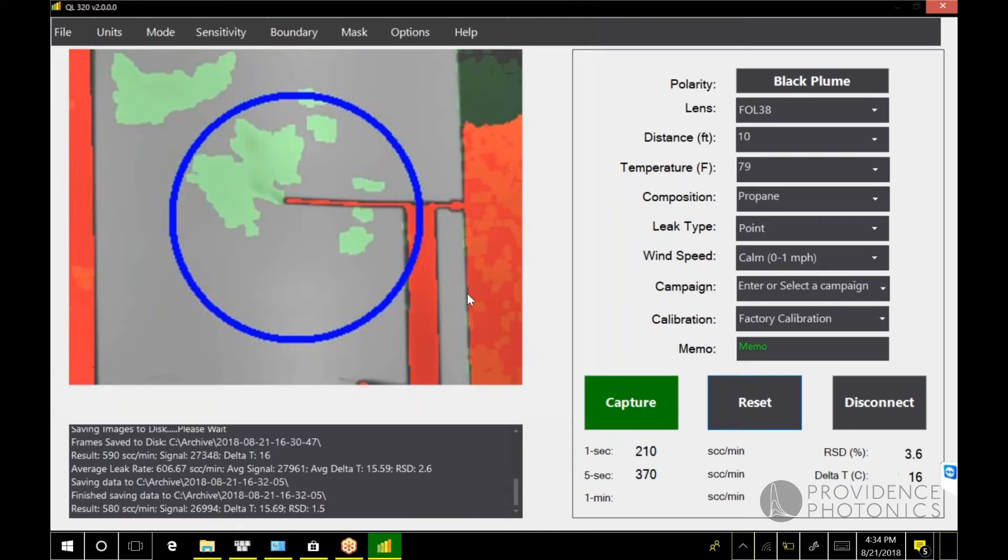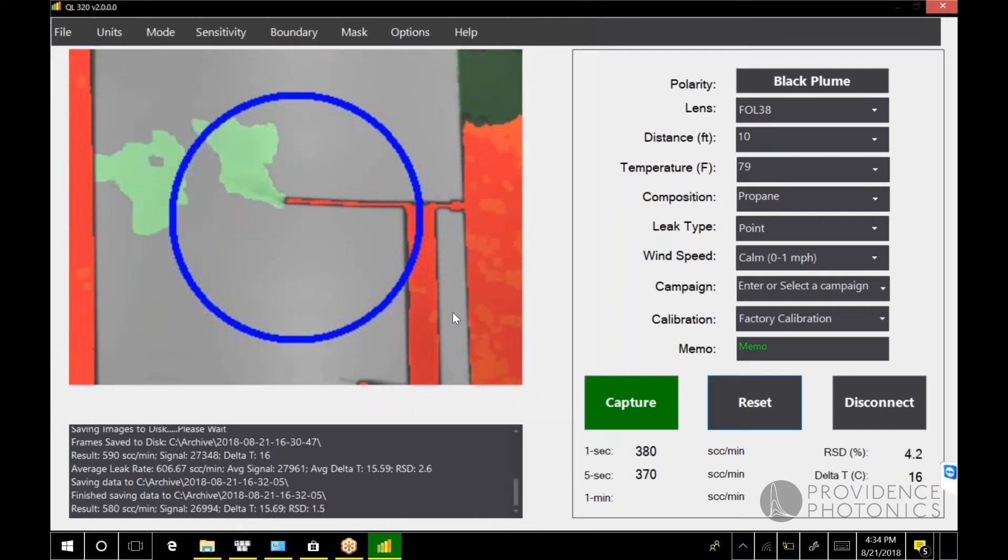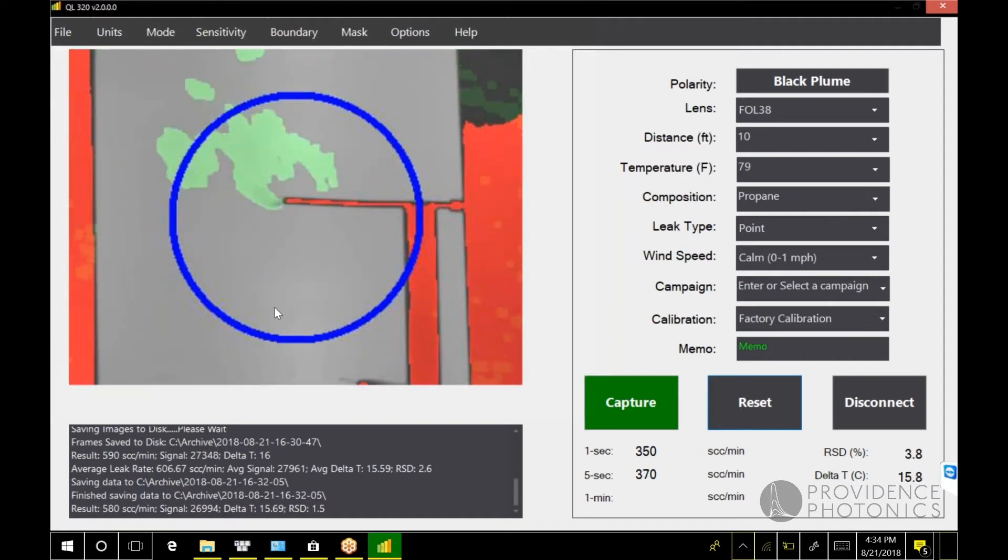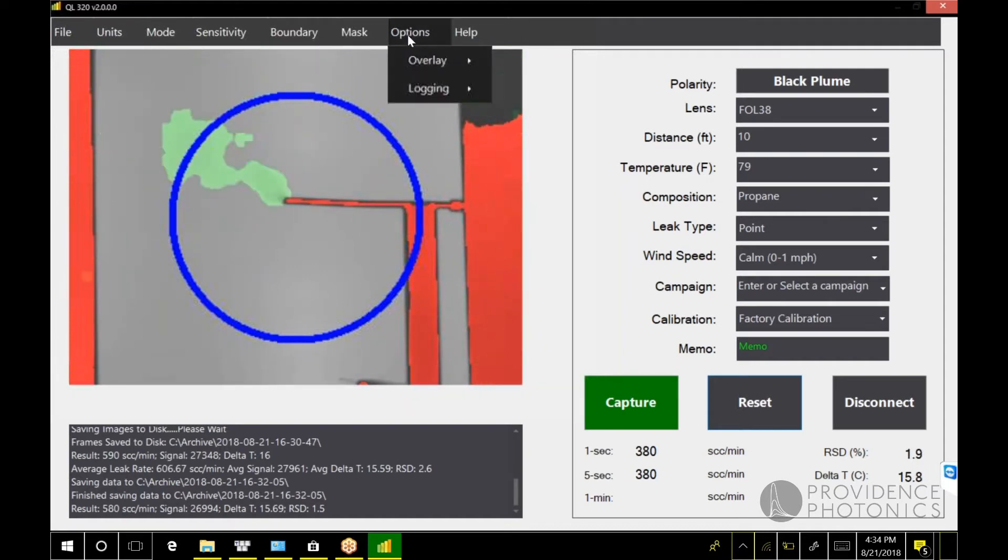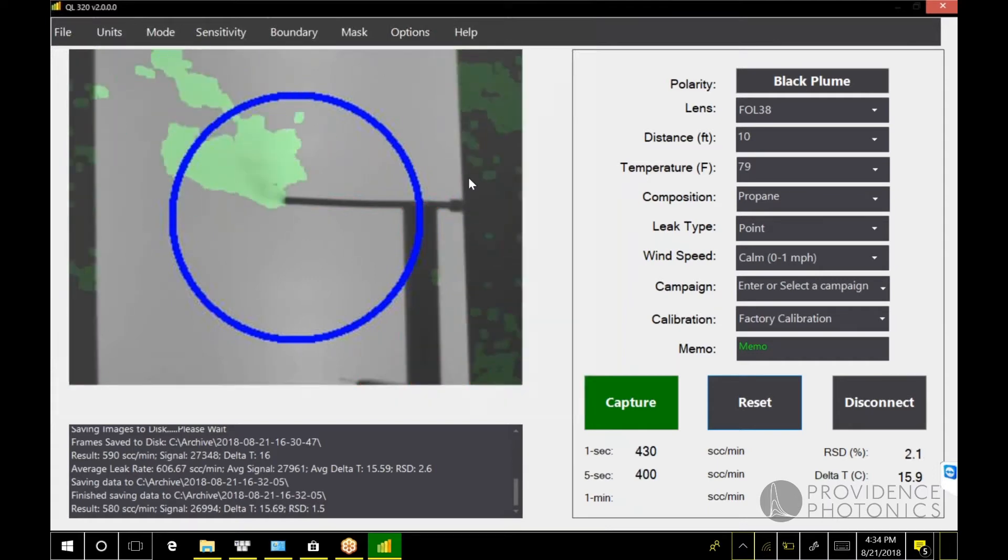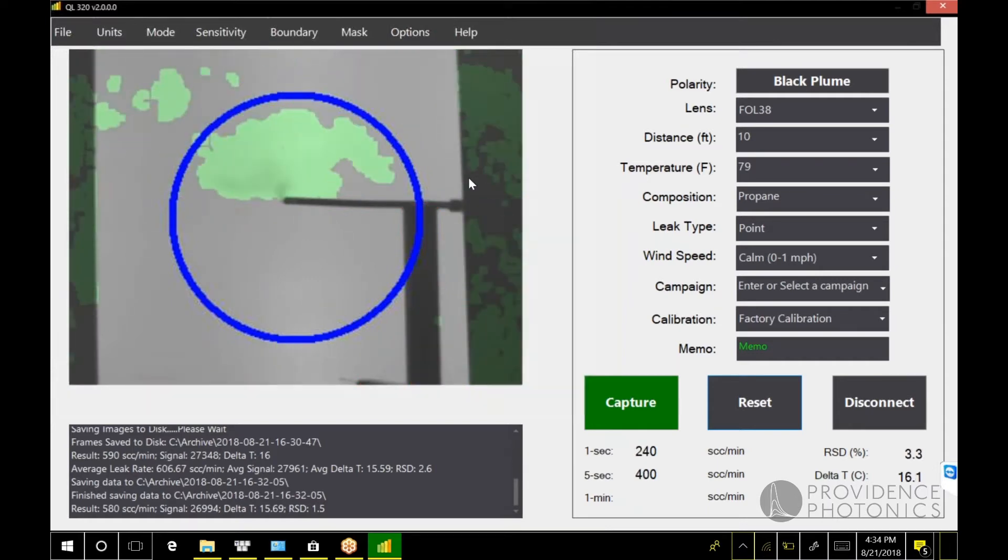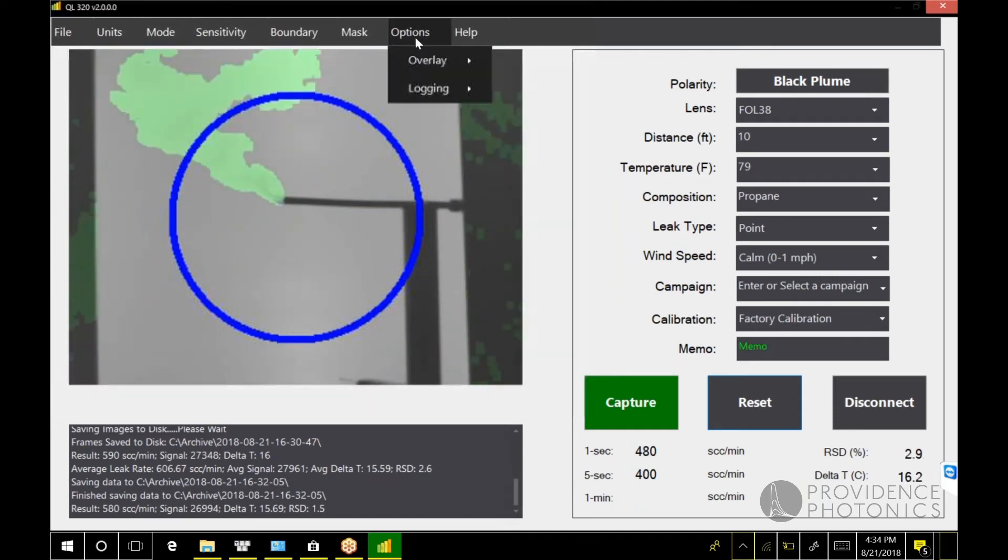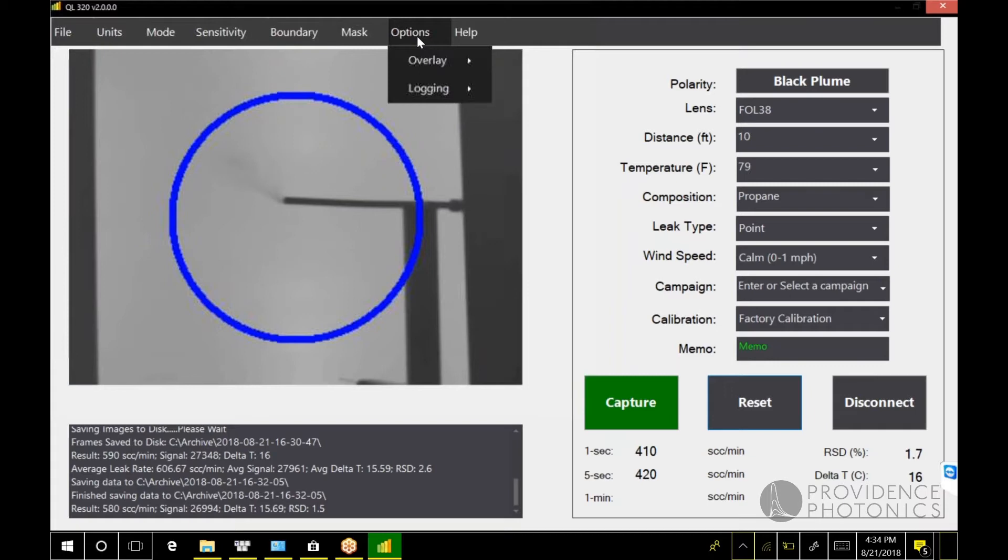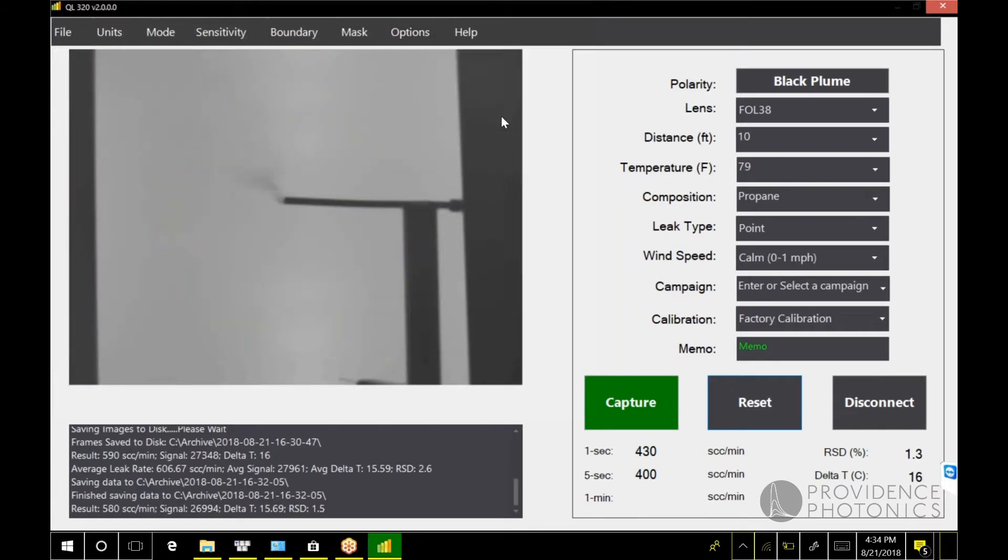If you have a previous version of QL 320, this is analogous to the screening mode. The parts that you see that are red don't have enough delta T to apply this method, so you wouldn't want to try and measure the plume in those areas. If you ever want to turn that overlay off, you can simply come here to overlay and turn it off. You can also turn off the plume overlay.